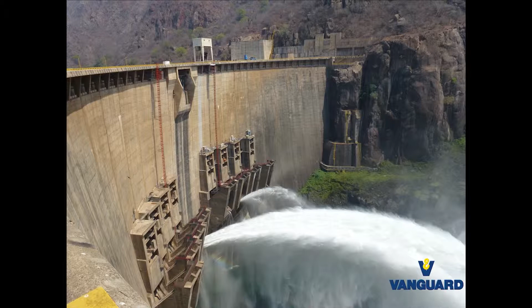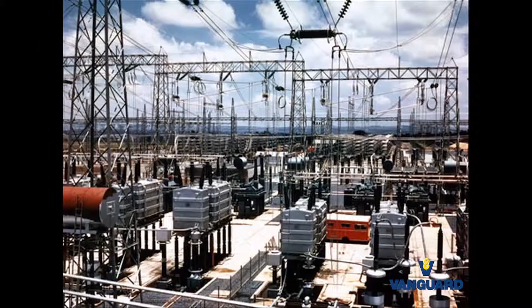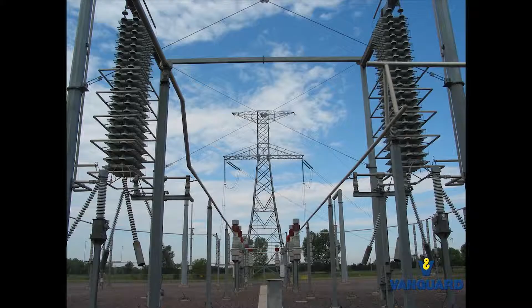Using a high-voltage direct current overhead line, the electricity travels over 1,400 kilometers to the Apollo converter station in northern Johannesburg, where it is fed into the city's grid. The export sale of this electricity is a vital income not only for the Tete province, but for Mozambique as a whole.